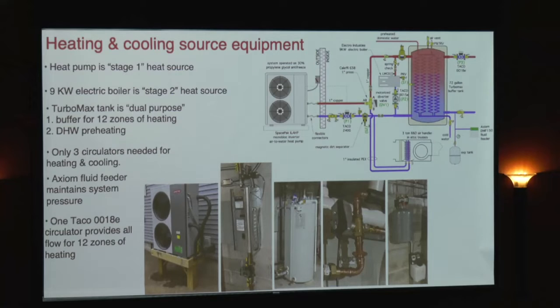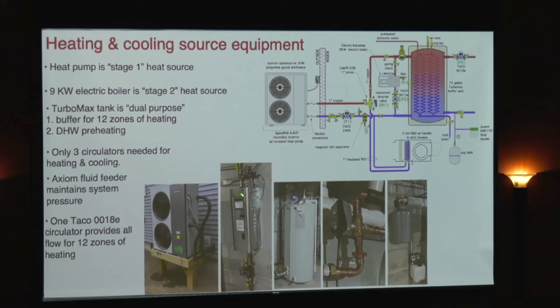So here's some photos of it, just kind of looking at the equipment. There's the heat pump up on a stand. These are flexible hoses with a stainless steel braiding on the outside. They're all insulated now, and it doesn't show it here. They're going to be wrapped with an ultraviolet resistive tape too, so that insulation doesn't degrade over time with sunlight. There's the electric boiler, very small, like 16 inches tall, maybe 6 inches wide, 9 kW.